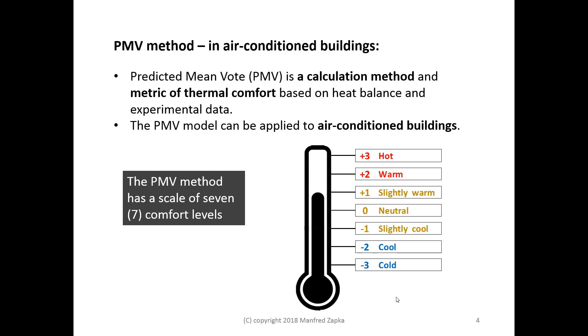The PMV defines seven scales of comfort level between plus 3 and minus 3. In the middle, 0 is neutral — you can neither feel warm nor cold. Going up: slightly warm, warm, and hot; plus 3 is hot. On the other side, minus 1, minus 2, minus 3 determine the degree of increasing coldness.